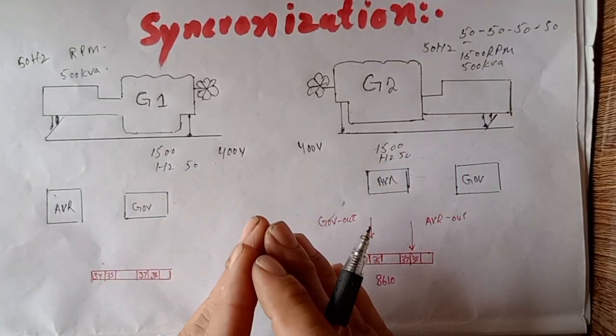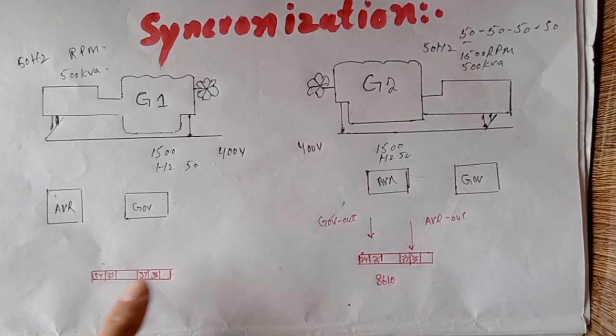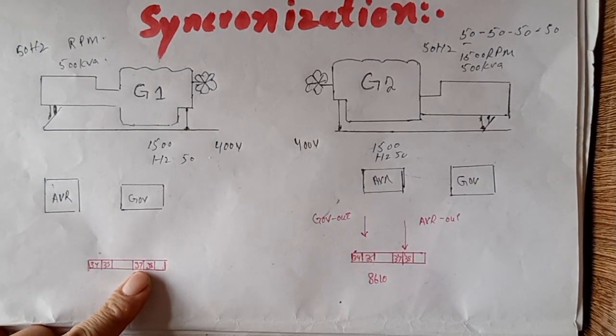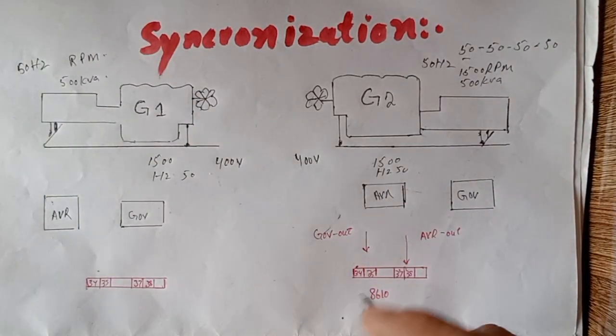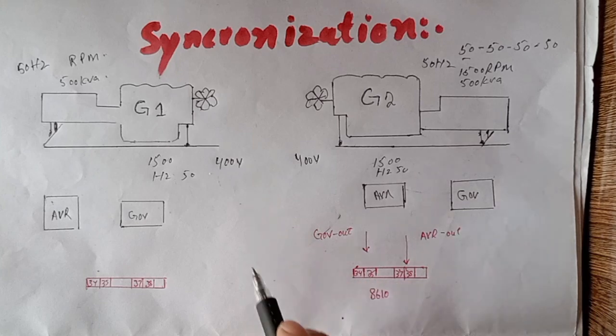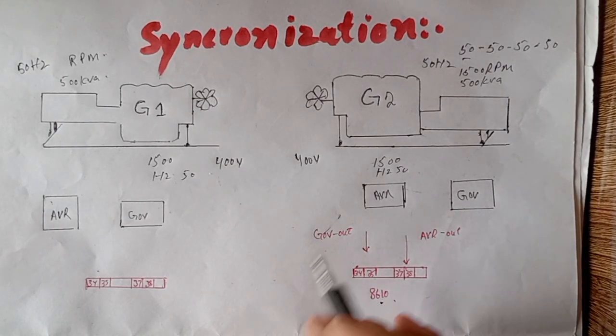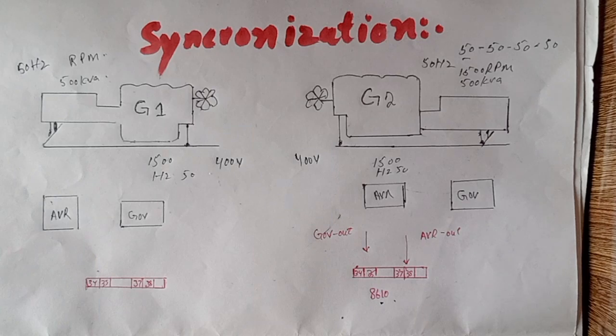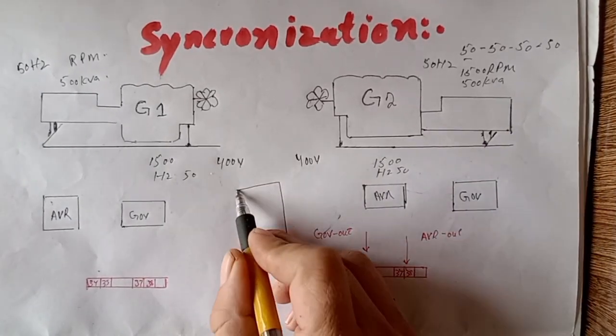Now we have the same type of generators with the same rating, frequency, and voltage. We need to install a synchronization controller. Nowadays, the DSE 8610 controller is widely used for synchronization and parallel operation of generators. We want to parallel two generators for one load — this is our bus bar, taken from the circuit breaker.